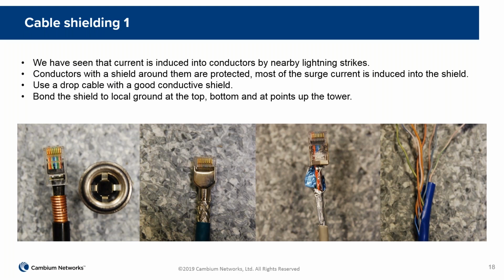So we want a shield which covers the whole cable. We want it to have good conductivity, to carry that current well, and we want to be able to bond that shield to ground at regular points, at the top and at the bottom, and depending on the height of the tower, along the tower itself.